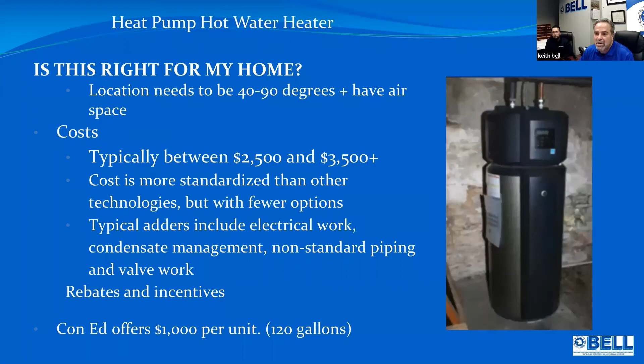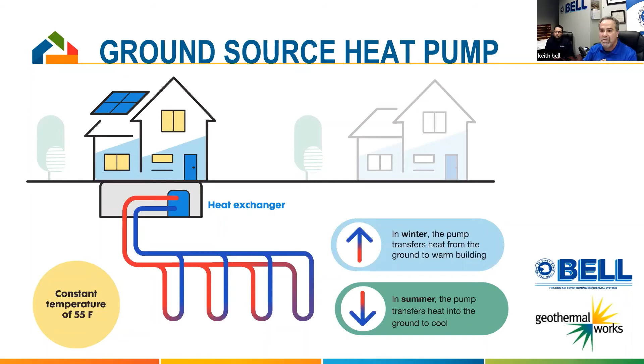So ground source heat pump. So now we're talking about pulling heat from one place to the other. The reason why geothermal is much more efficient is because now instead of trying to pull the heat out of that cold outside air when it gets cold outside, it always has a nice steady 50-degree source to pull the heat out of. And similarly in the summertime, when you're air conditioning, you want to reject heat. Your air conditioning unit rejects heat to 90, 100-degree air, where the geothermal rejects heat to the nice 50-degree ground. And that's why the efficiency is much higher. They're closer to 4 to 5 to 1 is the geothermal runs, and the air source go 3 to 4 to 1. So your ratio is better with the geo.